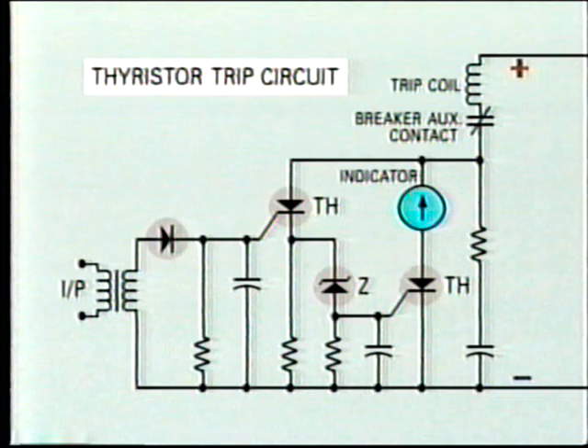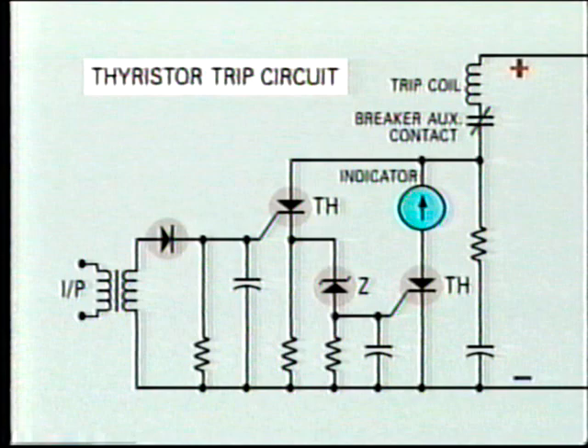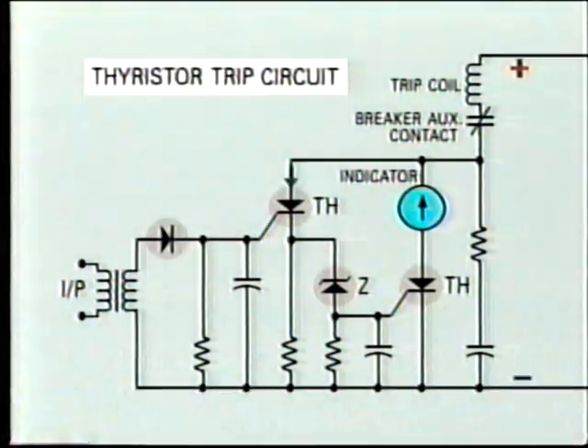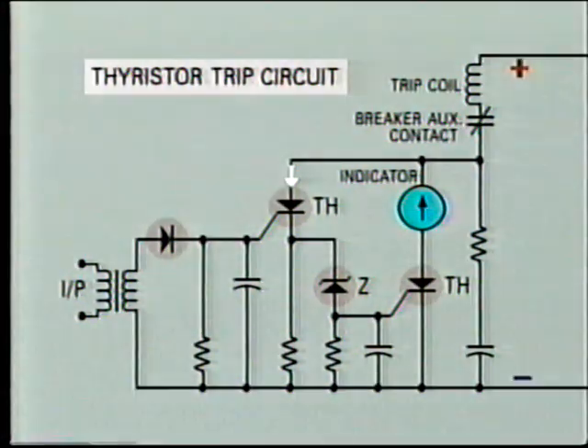In practice, the output circuit of the relay would be a little more complicated, like this. The input signal is fed in through the isolating transformer. The capacitor, located here, is to prevent the thyristor from being triggered by spurious pulses, which may be caused by interference. When the desired signal level is reached, the low-power thyristor is triggered, and this in turn triggers the main thyristor.